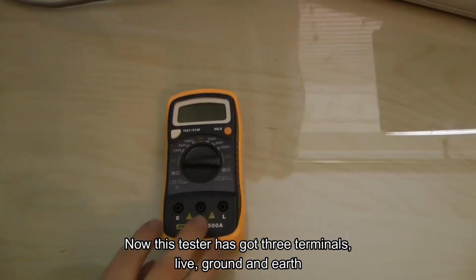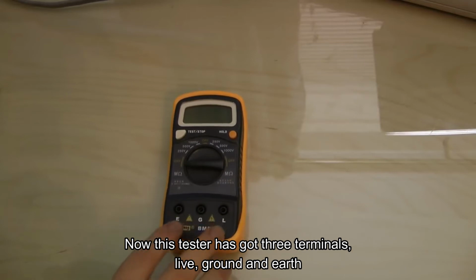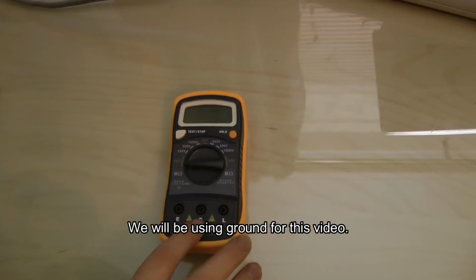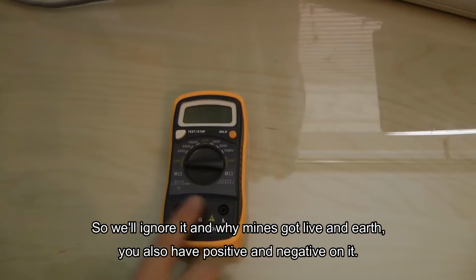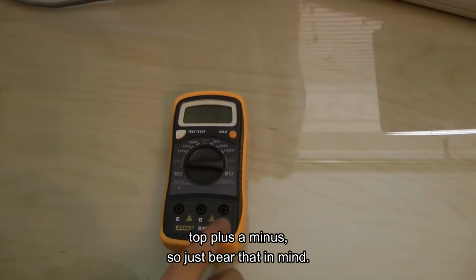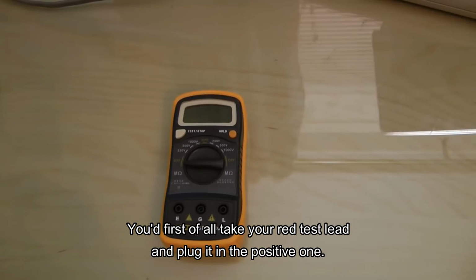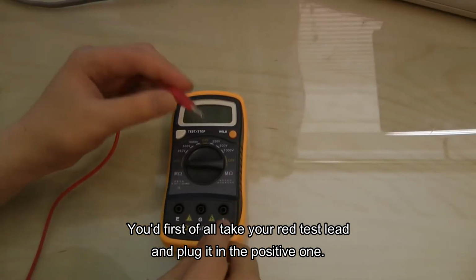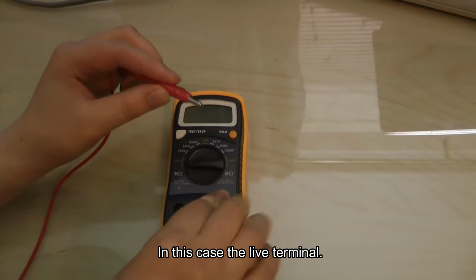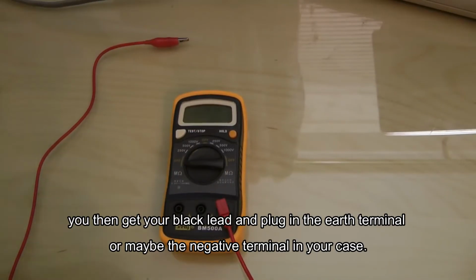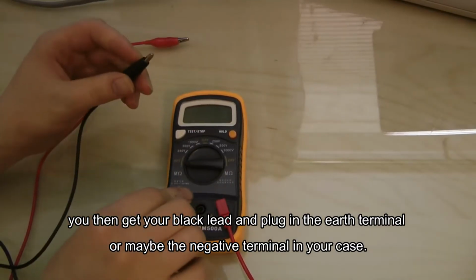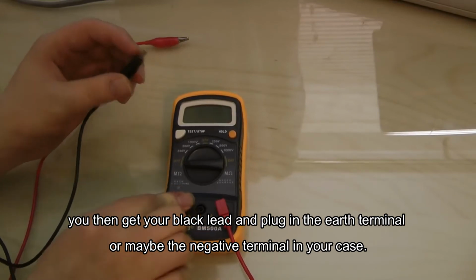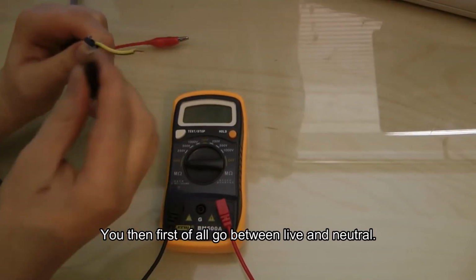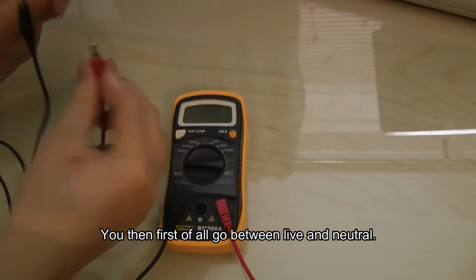Now, this tester has got three terminals: live, ground, and earth. We won't be using ground for this video, so we will ignore it. Mine's got live and earth, and you also have positive and negative on it, plus or minus, so just bear that in mind. You first of all take your red test lead and plug it in the positive one, in this case the live terminal. You then take your black lead and plug it in the earth terminal, or maybe the negative terminal in your case. You then first of all go between live and neutral.